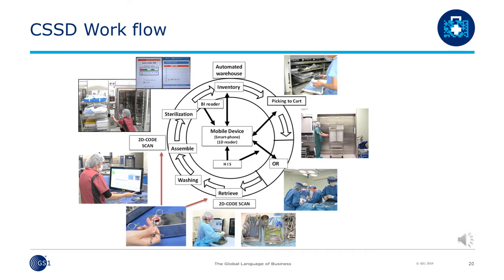Step 4. Inspection and assembly. Staff must check each item and notify the user if any part of the equipment is missing or damaged on receipt. Assemble the type and number according to the predetermined packing list. Packaging and sterilization. The medical devices are wrapped in medical packaging material and the packaged products sterilized. For quality control, set biological indicator and chemical indicator.